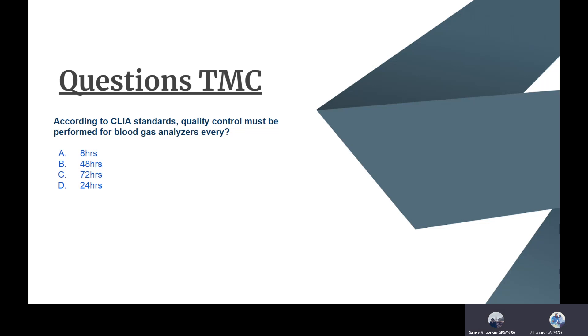Next we have a TMC question from our TMC that we took last week. It says, according to CLIA standards, quality control must be performed for blood gas analyzers every blank, and the answer is every eight hours. CLIA wants ABG machines to be calibrated every eight hours to make sure that they're accurate.